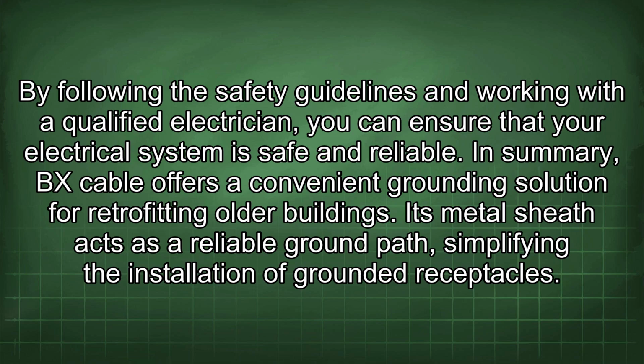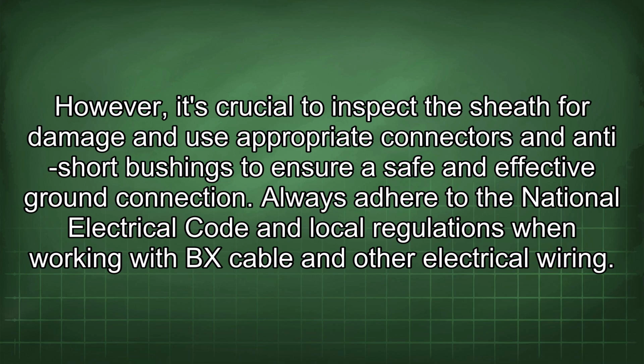In summary, BX cable offers a convenient grounding solution for retrofitting older buildings. Its metal sheath acts as a reliable ground path, simplifying the installation of grounded receptacles. However, it's crucial to inspect the sheath for damage and use appropriate connectors and anti-short bushings to ensure a safe and effective ground connection. Always adhere to the National Electrical Code and local regulations when working with BX cable and other electrical wiring.